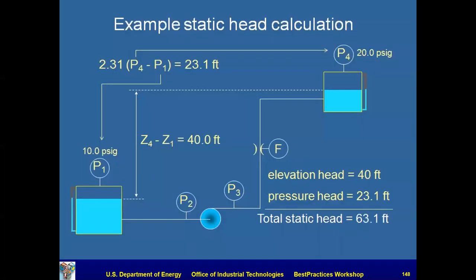So there you go. In this example, we've got 20 PSIG maintained at P4. We've got 10 at P1. So we subtract and we get 10 PSIG as the difference, times 2.31, 23.1. Elevation difference of 40 feet. So my total static head is 63.1 feet for this particular system. Now it's possible to put the suction tank up on a hill and have the discharge tank down in the valley. So then that elevation difference could be negative. So the static head can be negative, 0, or positive, just depending on how this works out for you.